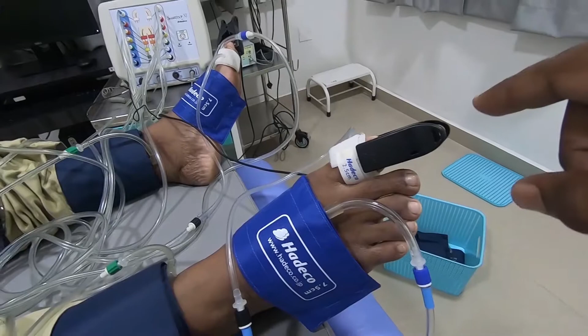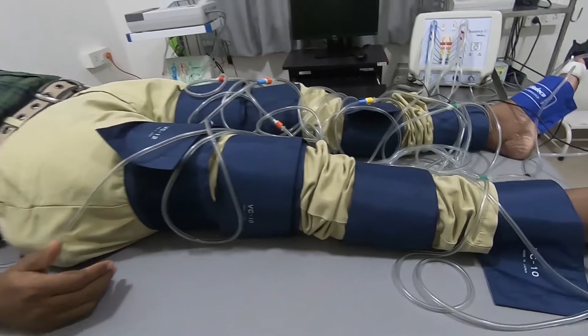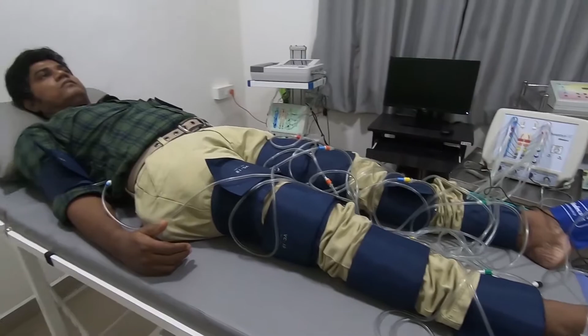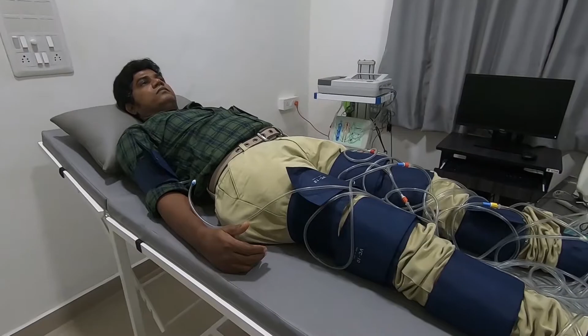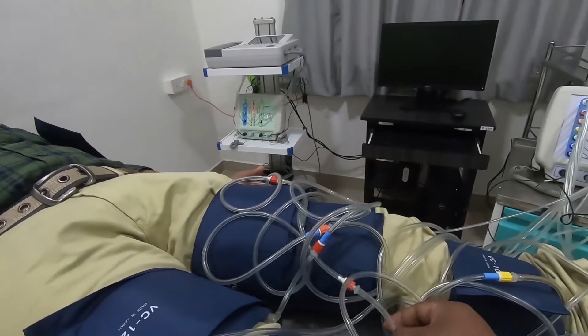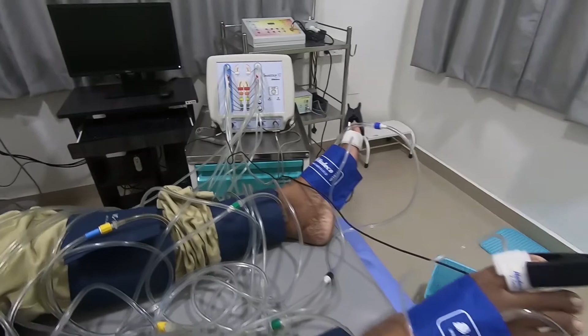And we are placing these PPG probes in the great toe. The cuff is wrapped in such a way that it should not be too kinked or have any blockage, and every tubing should face towards the machine before beginning the testing.